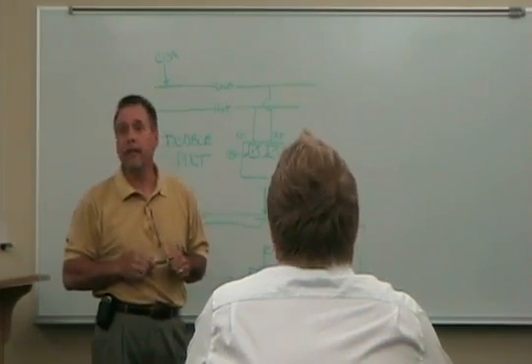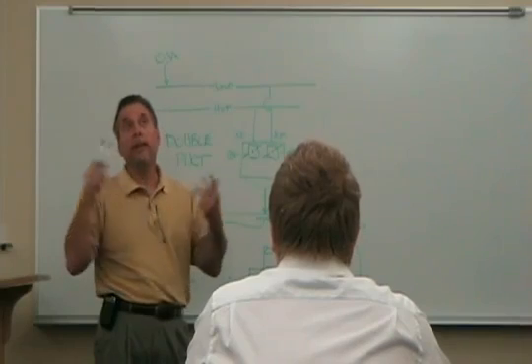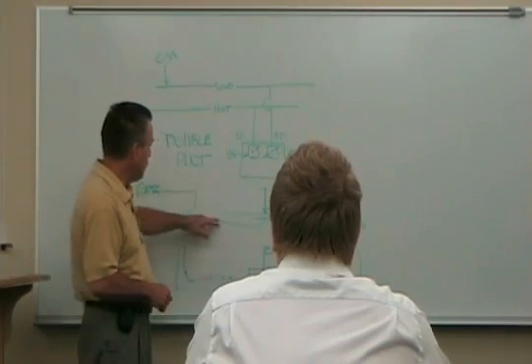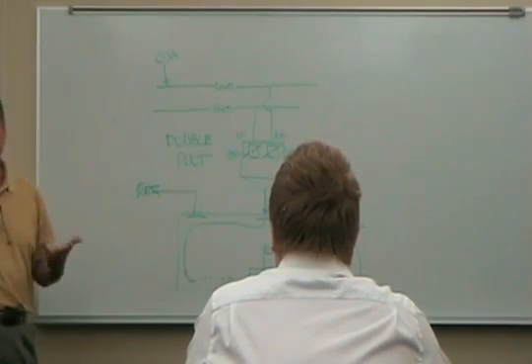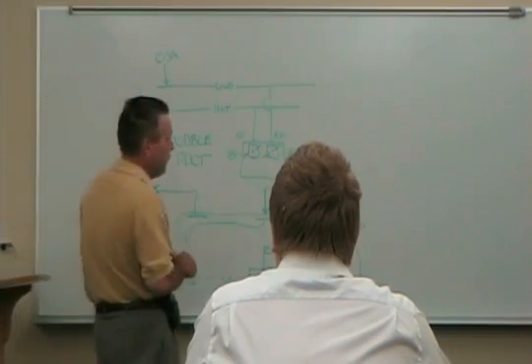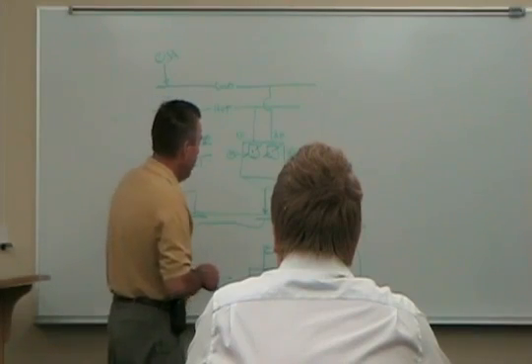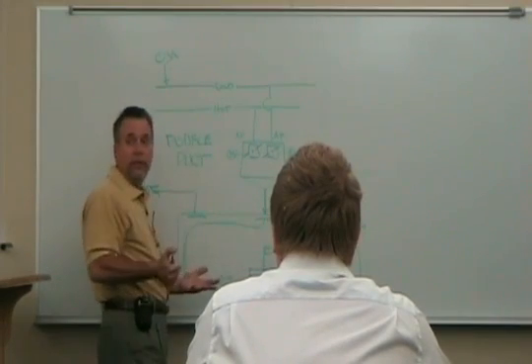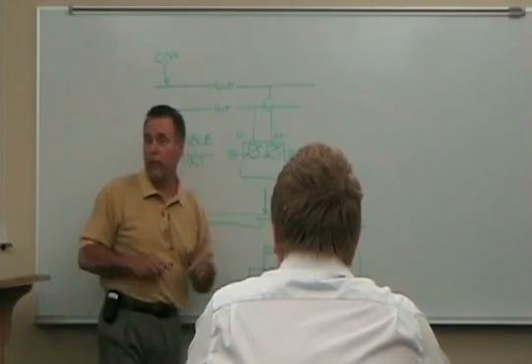There's various versions of this. But you can see these diffusers in various manufacturers like Krueger and Titus and Tuttle and Bailey. See it tested. No matter what the air temperature is, 55 or 100, that air gets pushed along the ceiling and diffused. They'll do smoke pattern tests. When you do a smoke pattern test on a VAV diffuser, especially even the hot air just doesn't know what to do. It still doesn't move along the ceiling. You see some manufacturers put different types of diffusers above the perforated plate. It just doesn't help. But that's all I wanted to mention, that in an air conditioning space, the intent is to move the air along the ceiling, diffuse into the space, become the same temperature as the room before you get into contact with your skin.